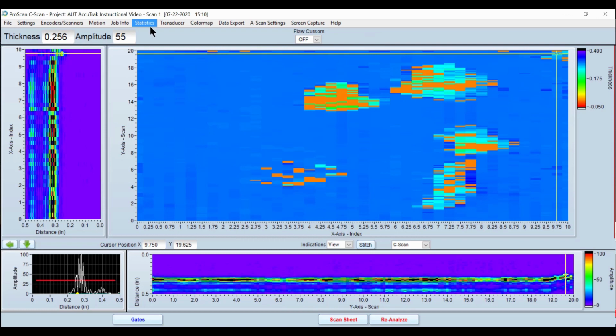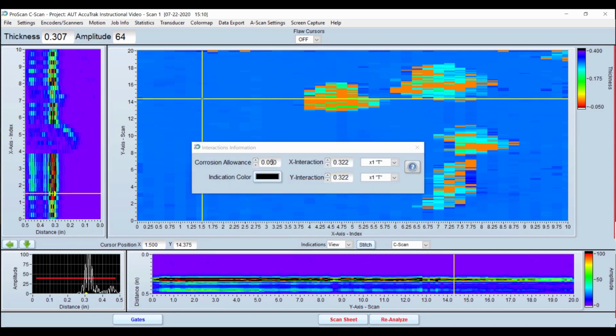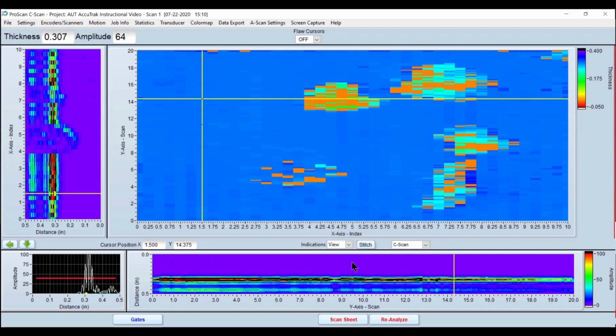So when we started this project, the client said, hey, we have a 50 mil corrosion allowance on this line. So we're going to go in and set up our auto indication features. So you would simply type in your 50 mils, which is already here. Now your XY interaction criteria as to whether a flaw interacts or not. This is pulled off of your material thickness. Same with the corrosion allowance. So if you have the appropriate thickness in here, which would be your average piece thickness, type in your corrosion allowance. Now we can simply go in and right click in the C-scan, go to auto indicate.